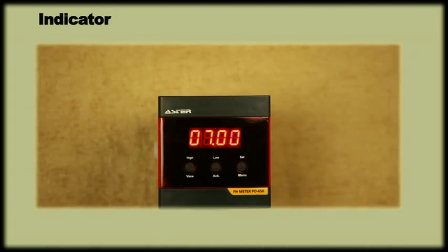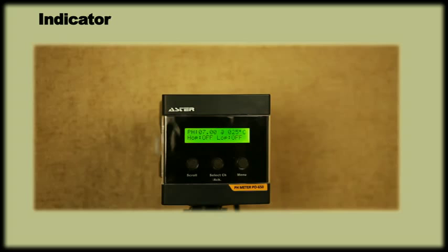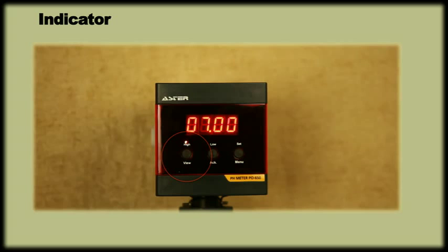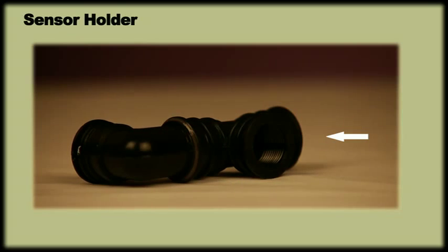Indicator. The indicator has a LED display. We also offer meters with dual line backlit display to simultaneously show temperature and pH. Our standard meter is supplied with high and low relay outputs. It gives signal to dosing pumps, hooters and valves. Sensor holder. The sensor is normally supplied with a 3/4 inch plastic sensor holder with female threading.